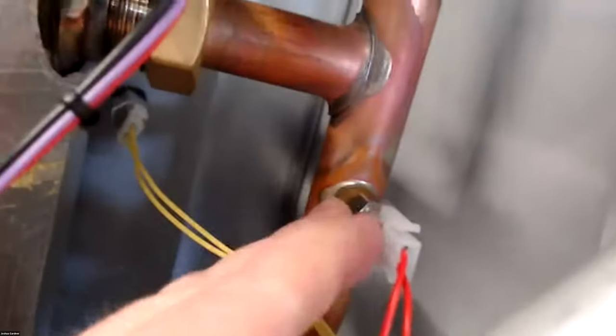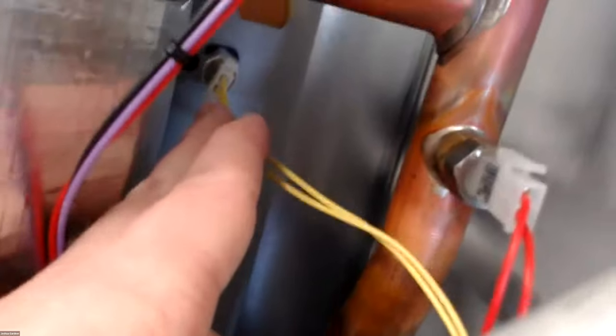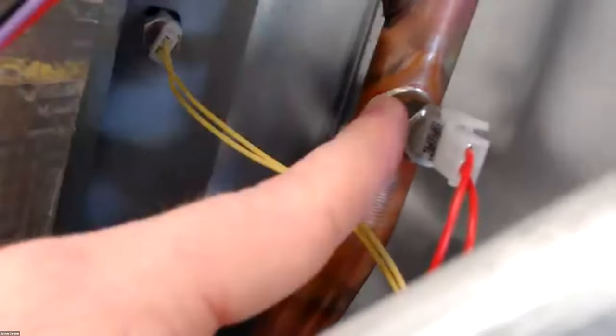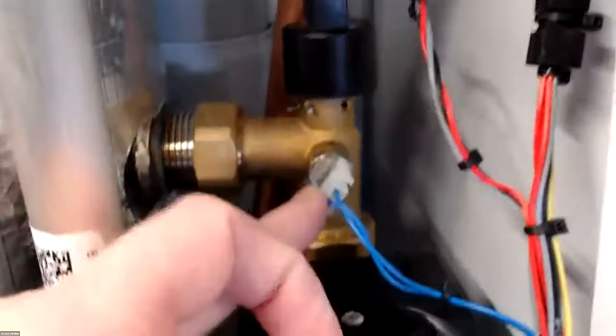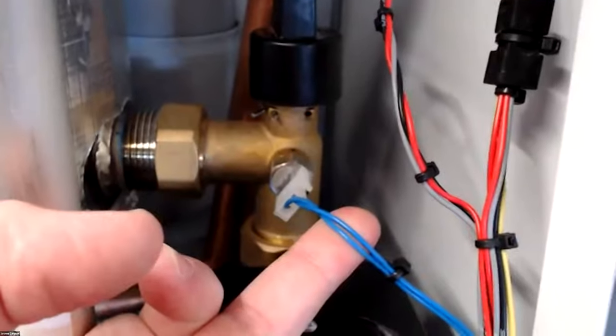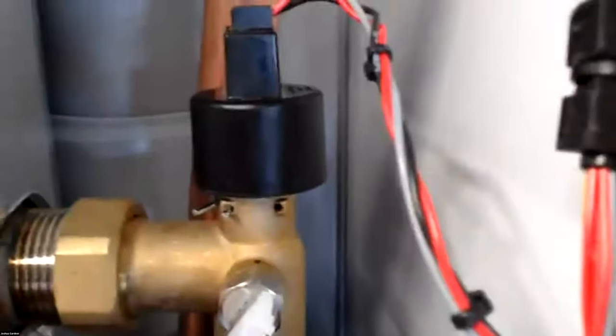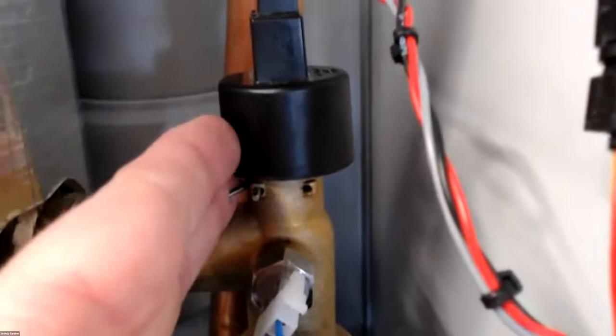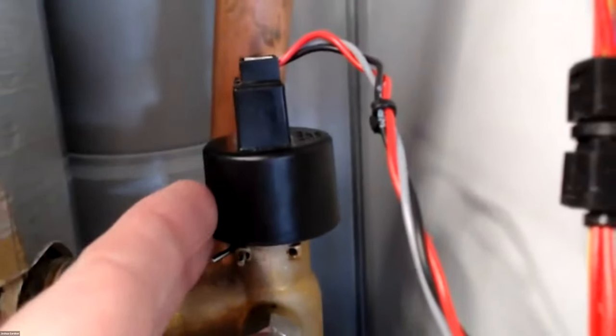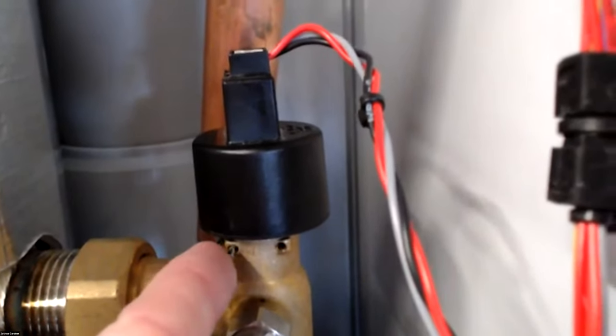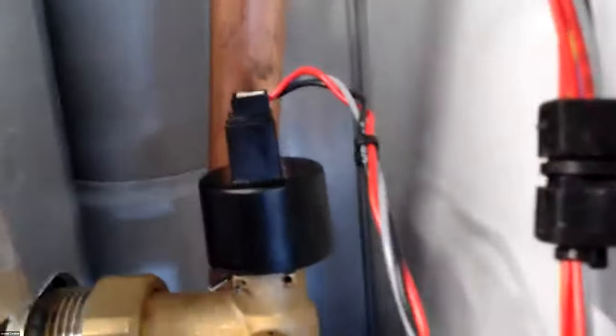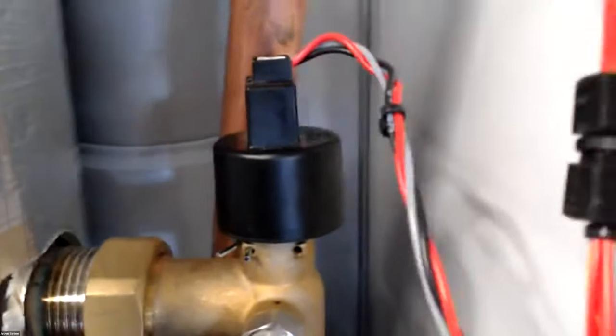And this sensor is different than our flue sensor, but our supply sensor, our return sensor, and our domestic sensor down here are all the same sensor. So you can stock one sensor and cover all those three. So working down, again, blue one, return temperature sensor right here. And then back in here, this is our low water cutoff, our pressure switch. Little pin right here, you pull this cotter pin, and this thing just pulls straight up and out. And that is a wet connection, it is a pressure sensor.